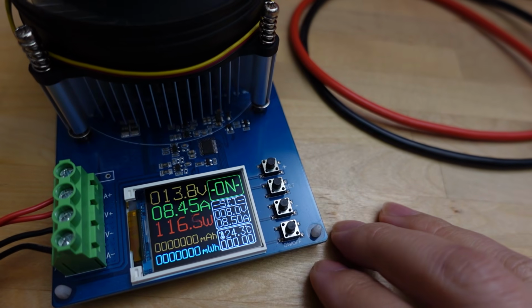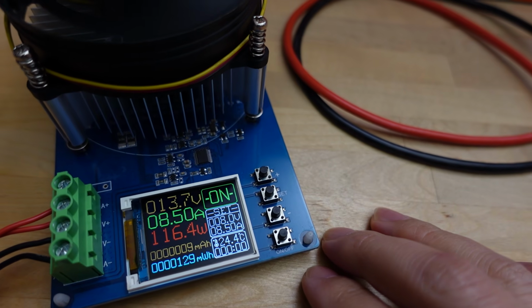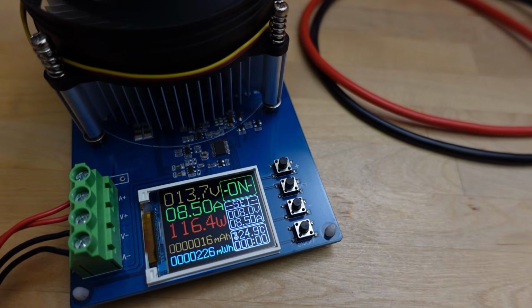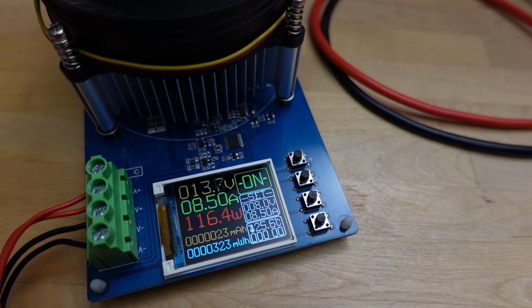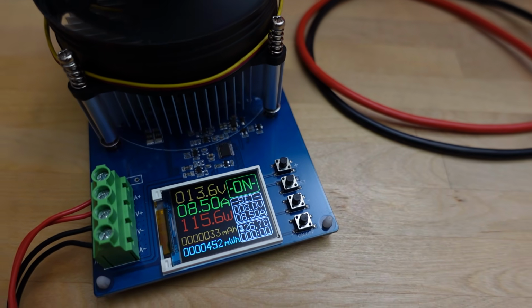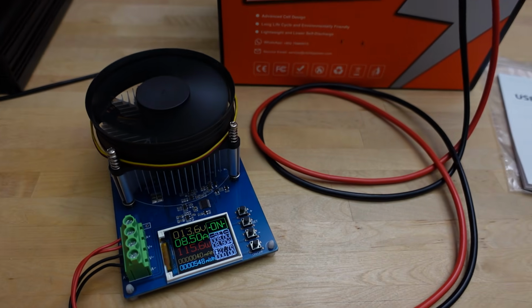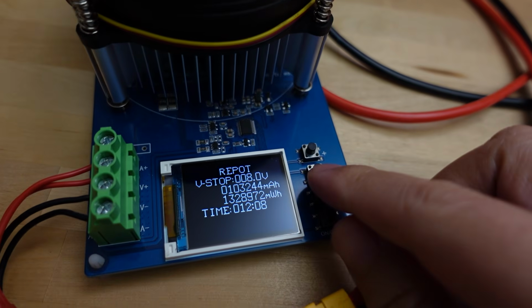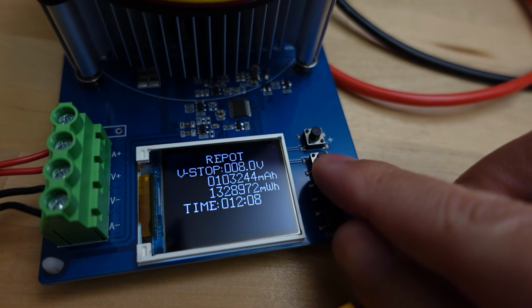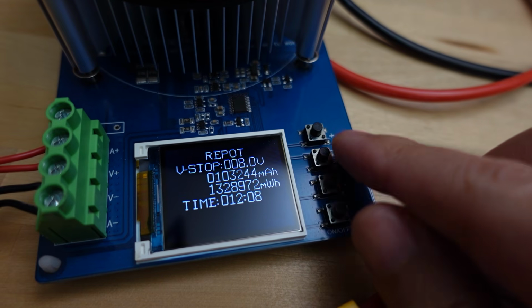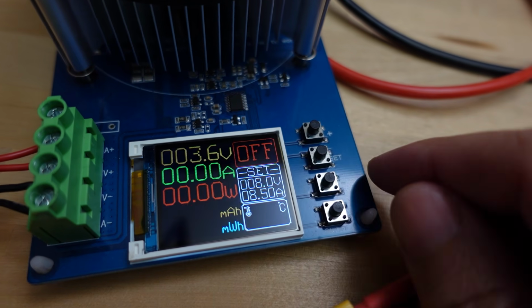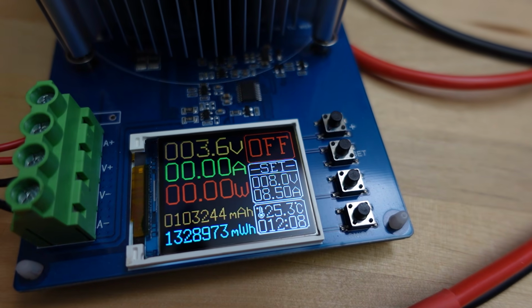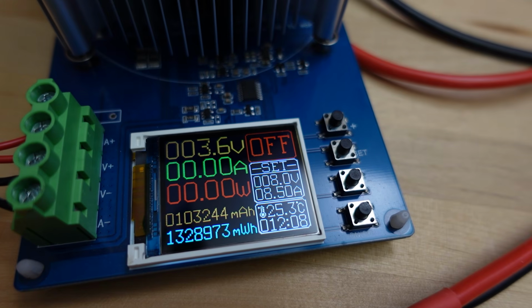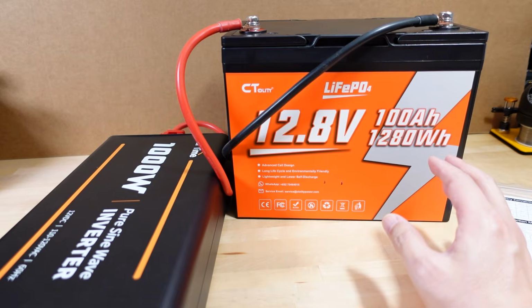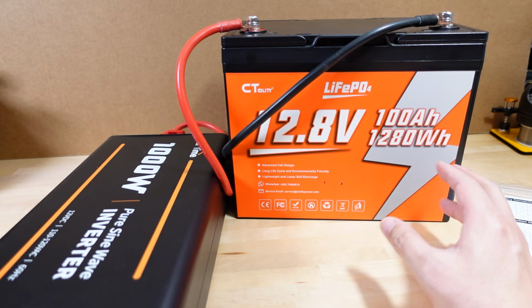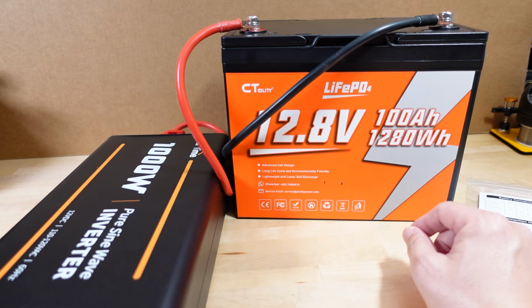Now in terms of the capacity of my particular sample here, I ran it on my standard capacity meter. I charged it all the way to full 100%, and then I put my capacity meter on and ran it all the way down to 0%, until basically the voltage cutoff kicked in and turned off the battery. Surprisingly, I got a very nice 1329 watt hours. The battery is rated for 1280 watt hours, and I got almost 50 watt hours more, so roughly 4% extra capacity compared to what is advertised. That's actually a little bit better than normal. Usually you'll get a little bit more, but not that much more. I typically get somewhere in the 1310 to 1315 range, so 1329 is quite a bit better than expected.